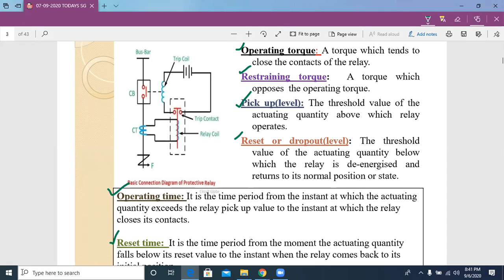So let's see, what is operating torque? Operating torque is nothing but the torque which tends to close the contacts of the relay. These are the relay contacts. Now, whenever a fault happens in this section, the CT will sense the fault current, and due to that fault current the relay coil is operated. When the relay coil is operated, electromagnetic torque is developed, and due to that electromagnetic torque, these contacts are going to be closed.